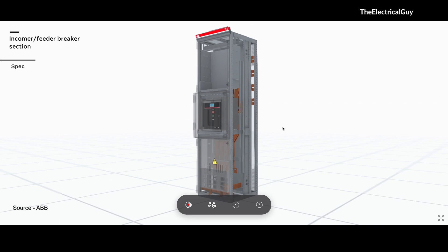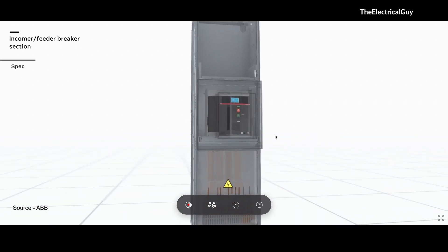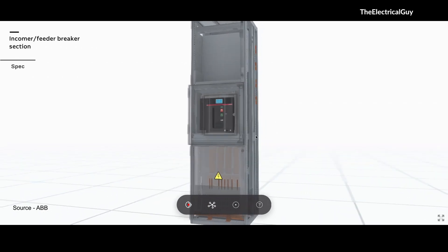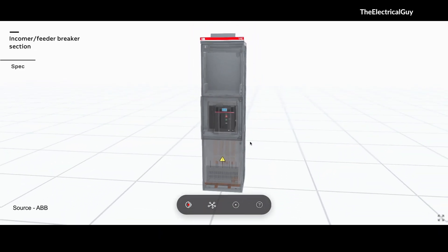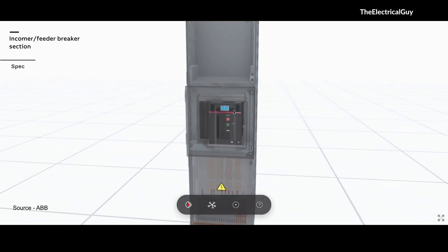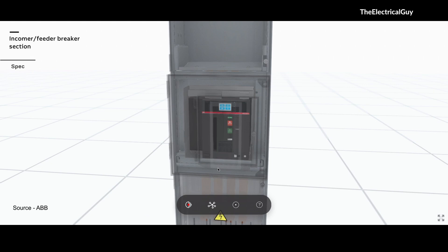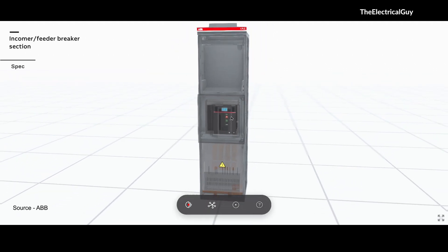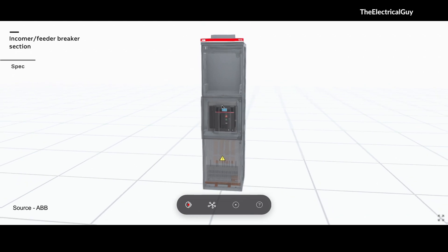These ACBs are capable of breaking short-time current up to 105 kA, and some breakers can go up to 200 kA, so the breaking capacity is huge. The good part about the circuit breaker in low voltage switchgear is that it comes with its own integrated relay, and you can make different protection settings here. When we go for medium or high voltage circuit breakers, that is not the case — we need a dedicated relay for that.